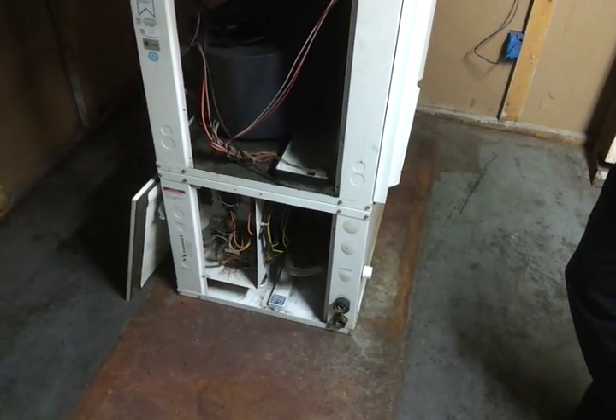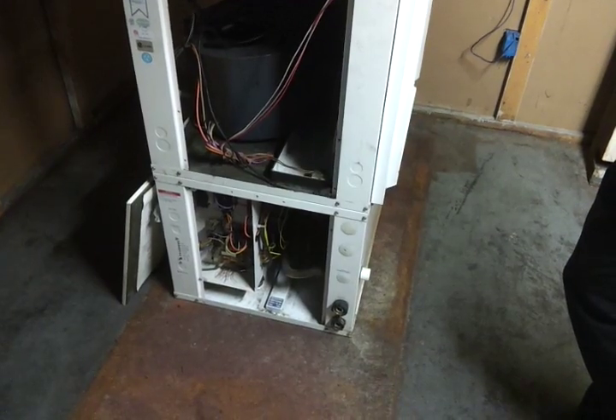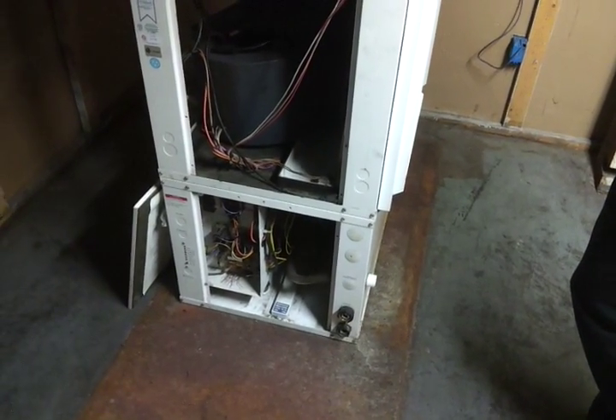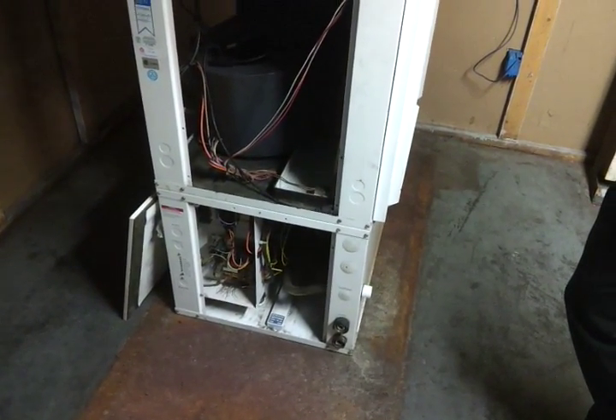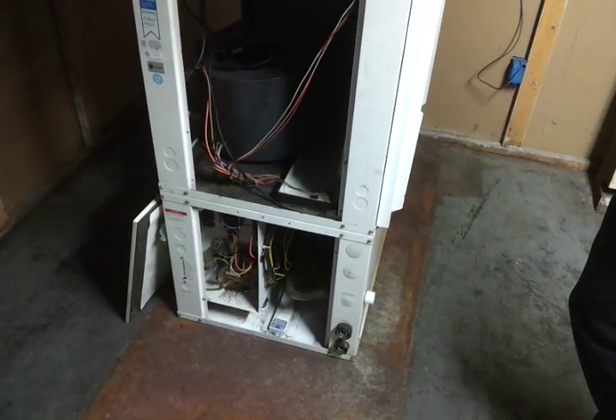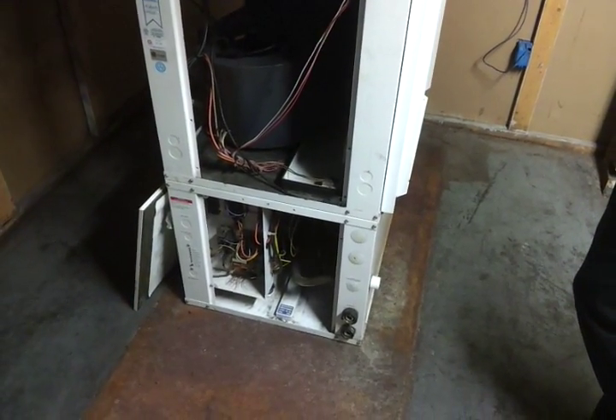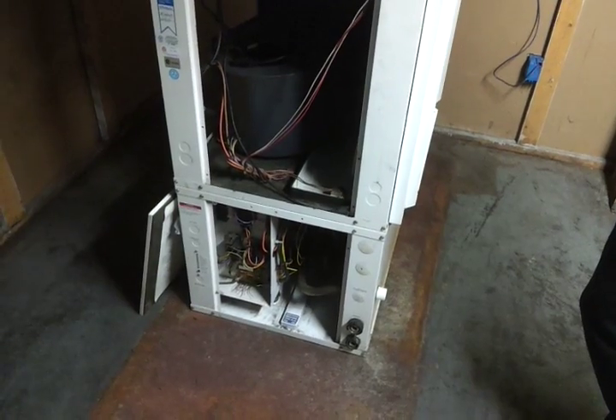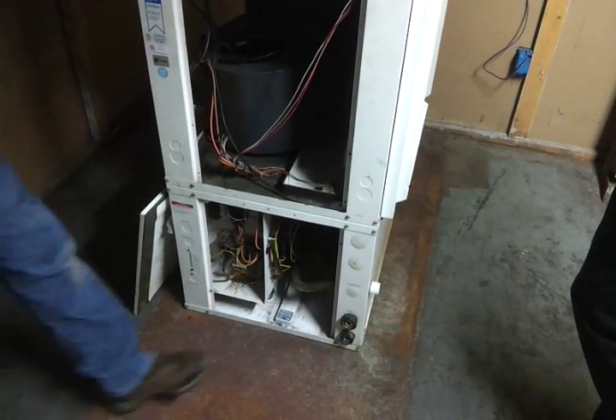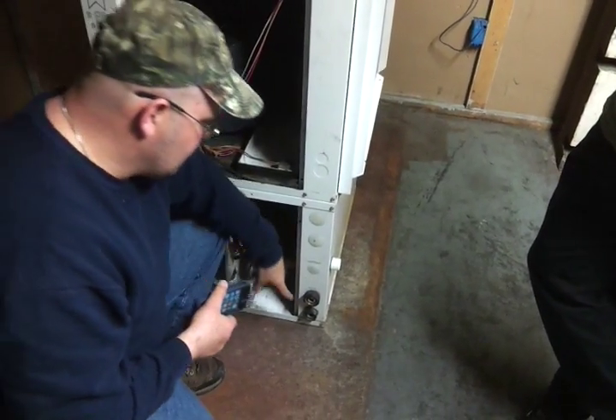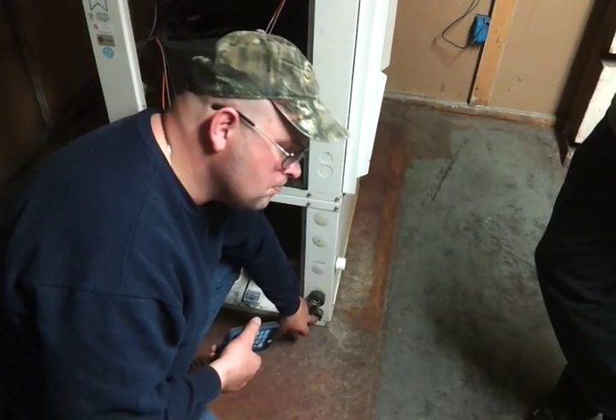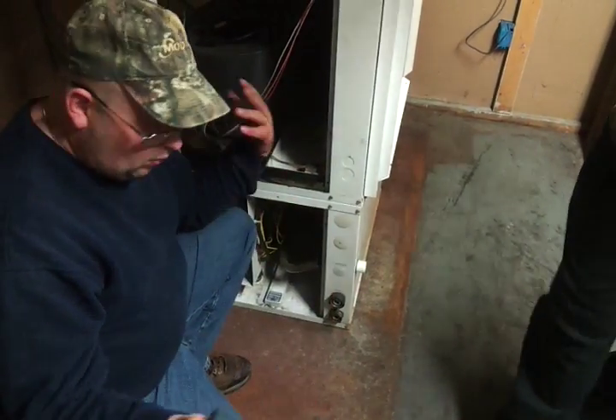Water in, water out. It would be preferable, instead of PVC right into that fitting, especially since you're not protected with any sensors here. At least a couple of sensors are not hooked up. What could happen is you could overheat or freeze, and the PVC here can melt and pop right off, and you'll have water all over.